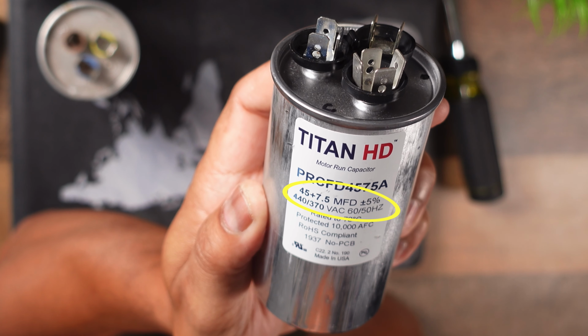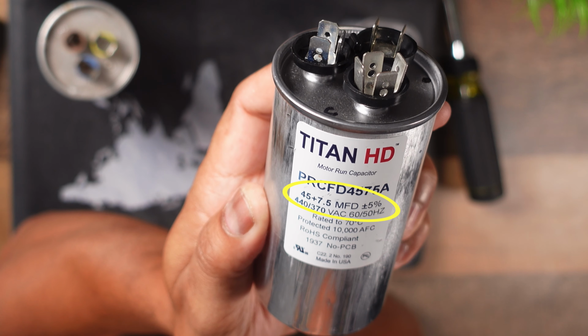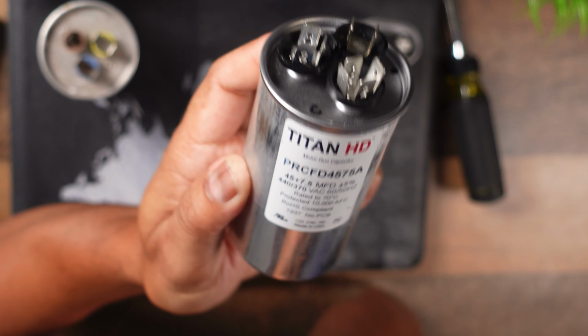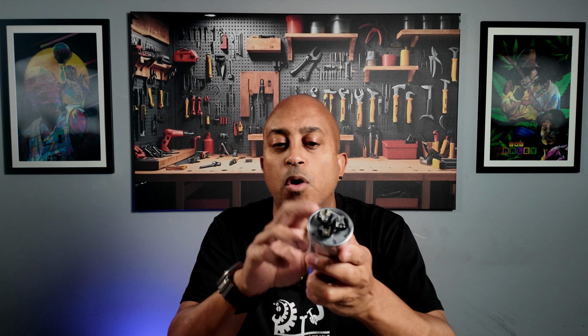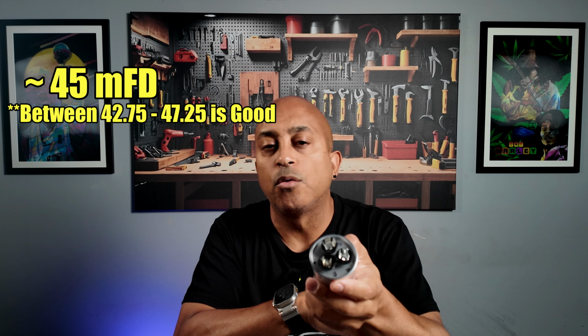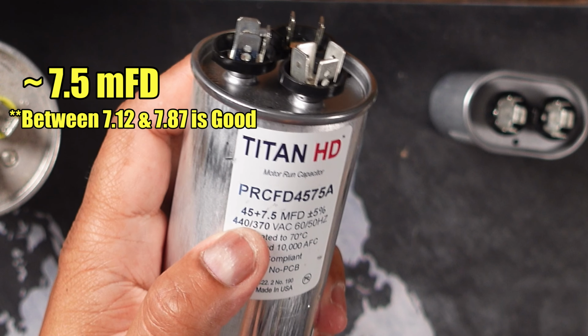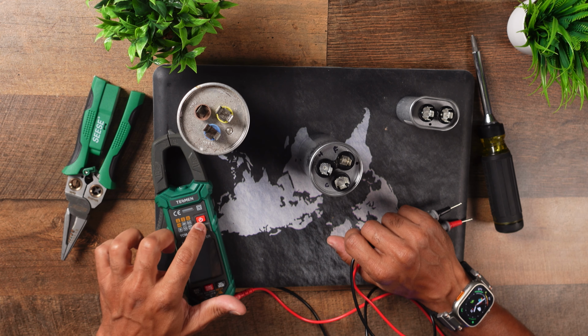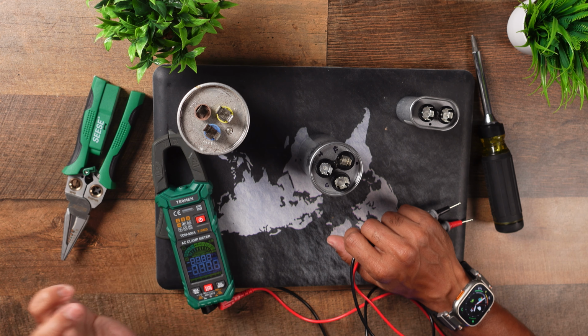Now, the first thing you want to do before you test your capacitors is know what size capacitor you have, and it's pretty simple. As you can see on mine, it says 45 plus 7.5 microfarad plus or minus 5%. This means one of the leads is going to read 45 microfarad and the other one is going to read 7.5 microfarad.